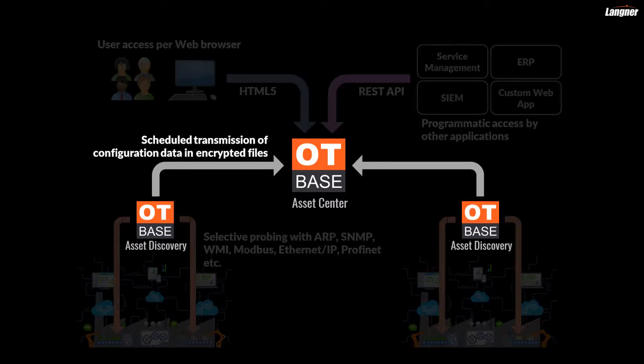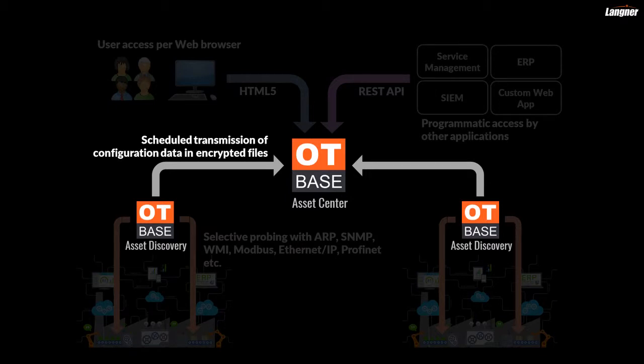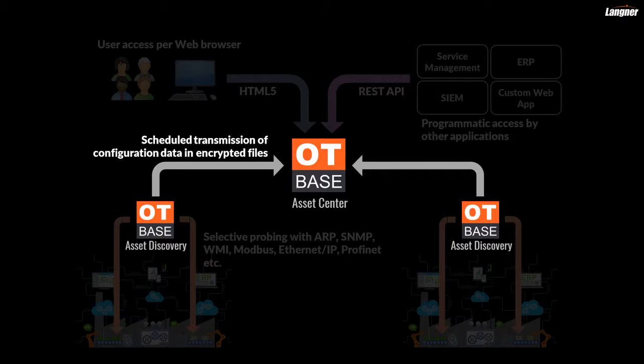This video only focuses on how to configure an OT-BASE asset discovery node properly for passing data to the OT-BASE asset center. Such configuration only needs to be done on the side of the asset discovery because the link is unidirectional. The OT-BASE asset center never talks back to an asset discovery node and therefore doesn't need to be configured. Data transport is achieved by passing a file from asset discovery to the asset center. Since these files are encrypted by default you don't need to worry about cyber security.